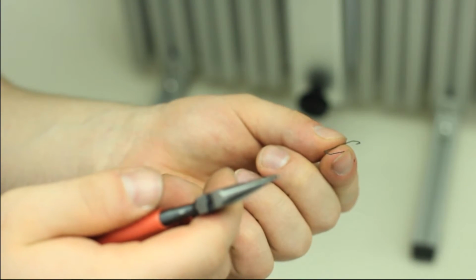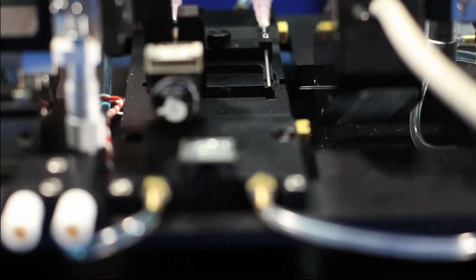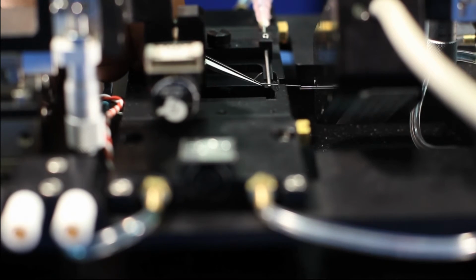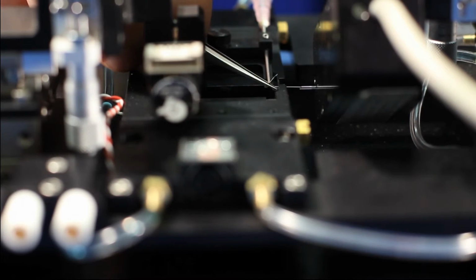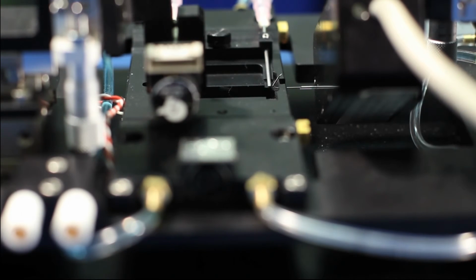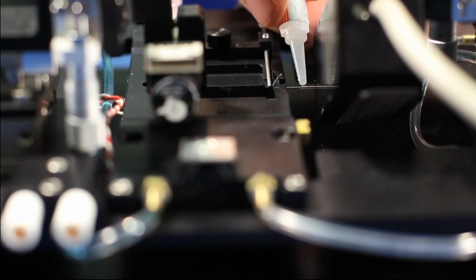Create a hook or pin from small gauge wire or tubing and slide it into the glass output tube of the transducer. This hook can be used for calibration or attachment to the sample. A little bit of paraffin wax or glue can be used to secure the hook.